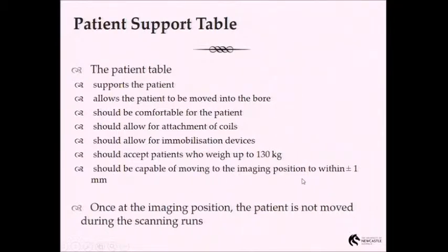The table needs to be capable of moving in very small increments. So when you put someone in the magnet, the first thing you do is create a landmark. You have to create a situation where you're telling the computer this is the zero point. When you're doing brain imaging, it's on the glabella.